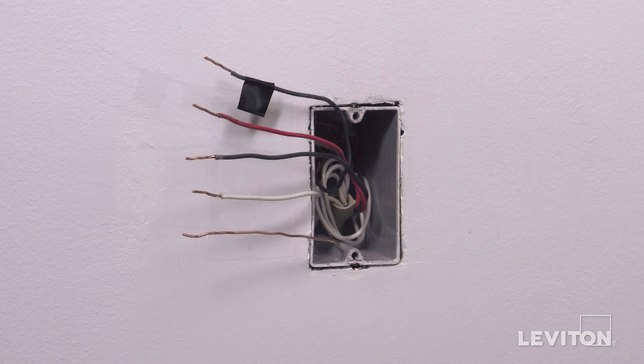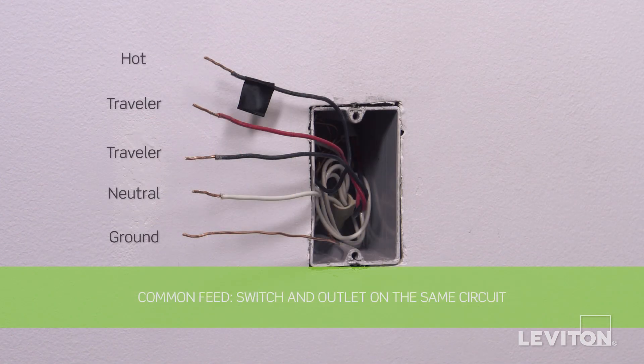The devices featured in this video may be installed to address different applications. Common feed: the lights are controlled by the three-way switch and another three-way switch at a different location, and the grounded outlet is on the same circuit. This method will require the following wires in the wall box: a black wire (the hot wire), a white wire (the neutral), two traveler wires, and a bare copper wire (the ground).